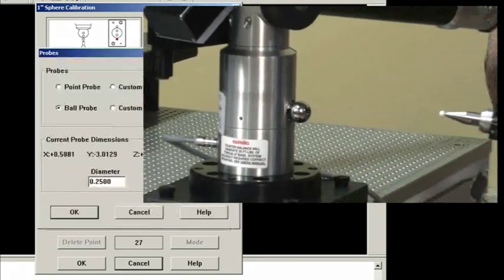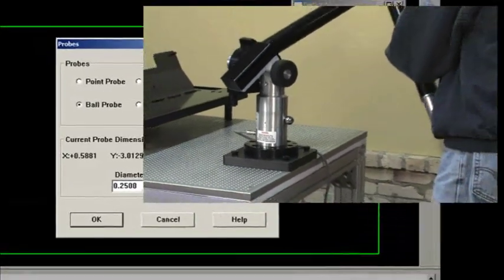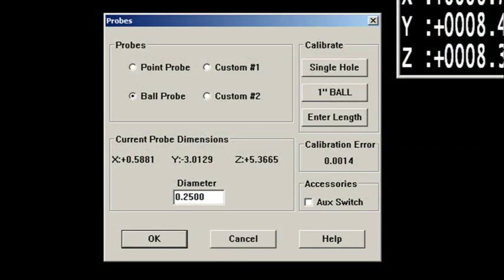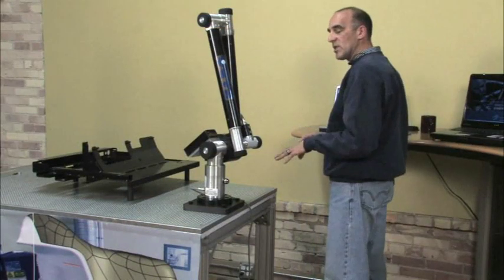There, now I've taken 27 points, and then Faro goes out, and it solves for the best fit center of that sphere. What it does is it samples all of those 27 points, and it gives me the calibration error. Notice that I've got 1.4 thou of deviation, or of calibration error. Well, that's pretty good. I can measure and feel confident that my measurement is within that 1.4 thou error. But I can't stress enough, just getting good at doing this calibration.